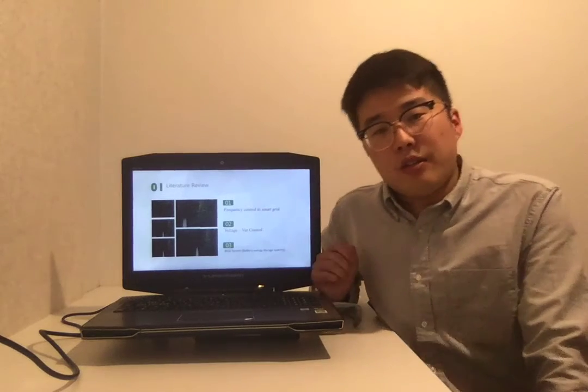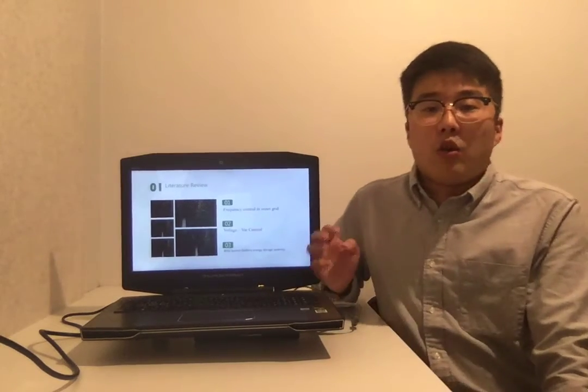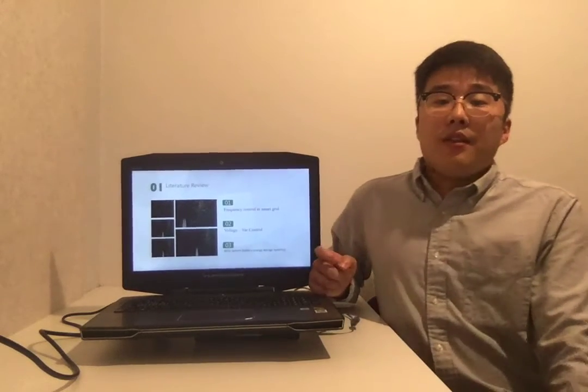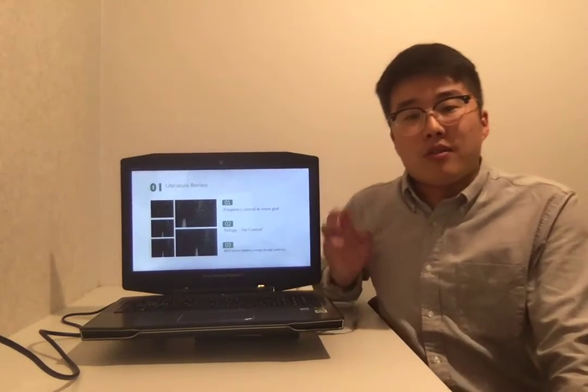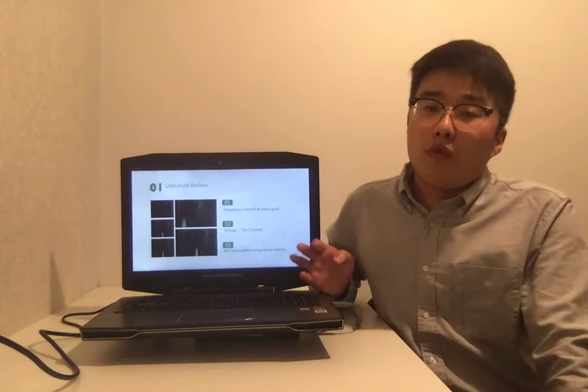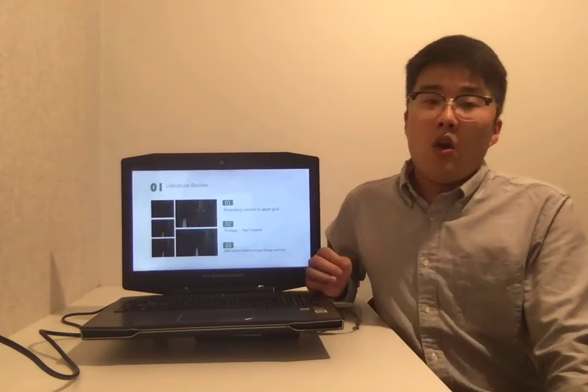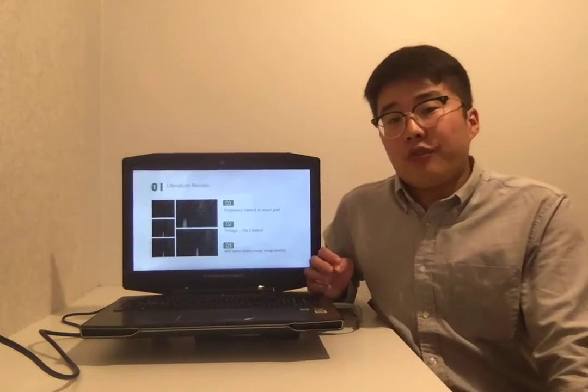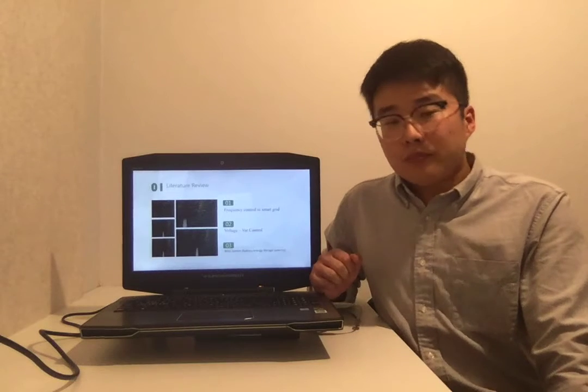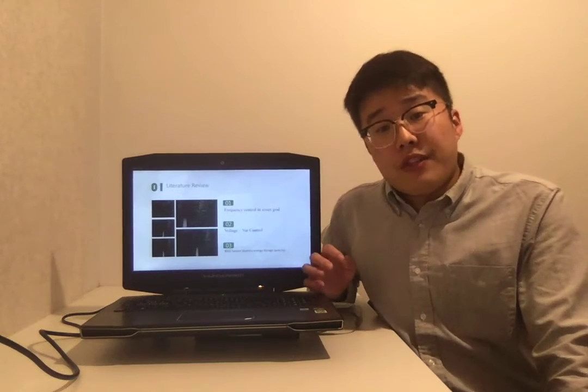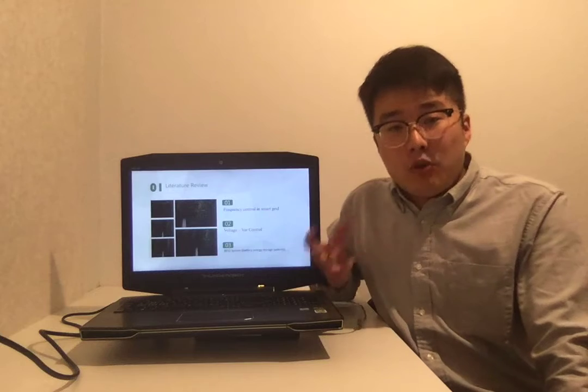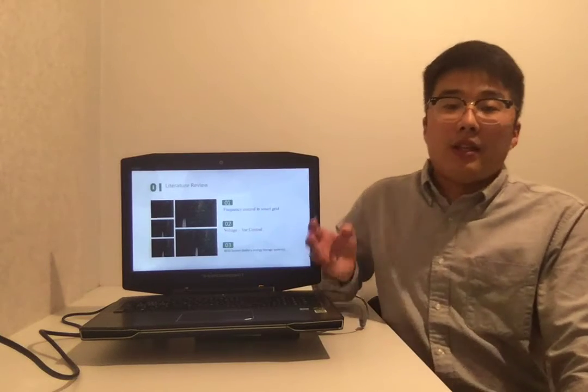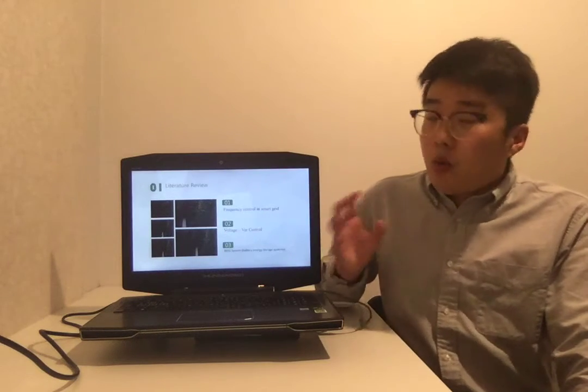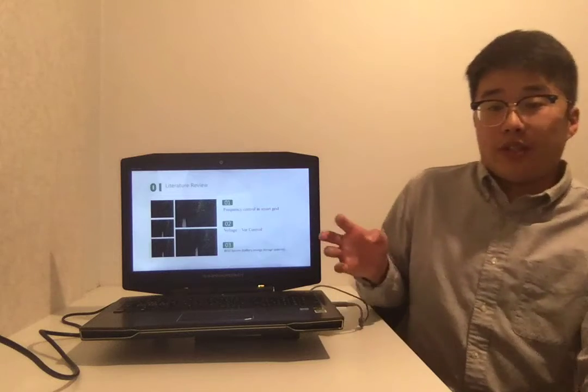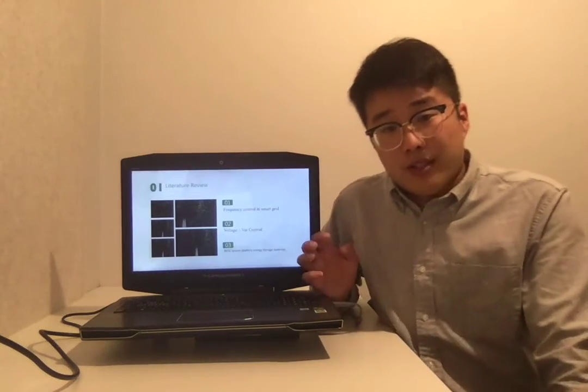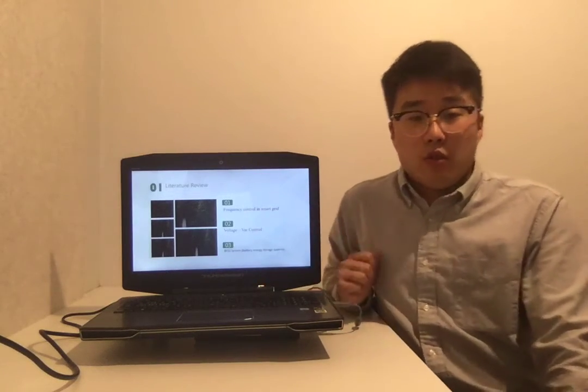The second method is a low voltage control method. This control method is to install a capacitor bank at the low voltage end of the transformer where different factories or different user groups are located. The advantage of this control method is it is very flexible and can compensate different reactive powers for different types of users in different regions, which is convenient for engineers to control.